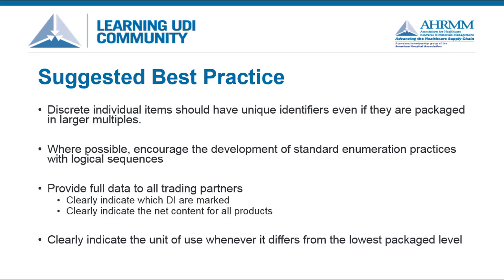First, all discrete items should be identified, even if they are packaged in larger multiples. For example, if you manufacture syringes in pharmacy trays, you should identify individual syringes within the lowest packaging level as well as at the tray or case level. Second, wherever possible, encourage the development of standard enumeration practices with logical sequences. If your policies permit, it may be beneficial to standardize around the use of specific identifiers related to specific packaging levels.